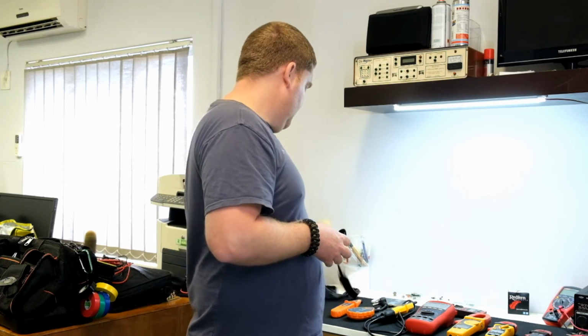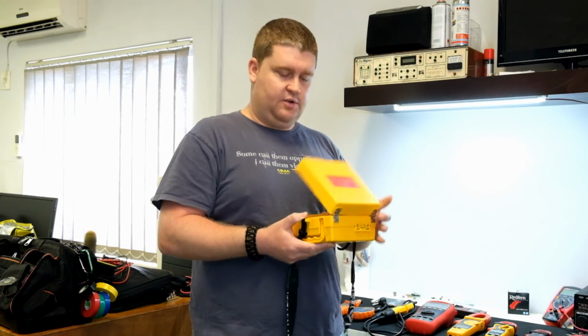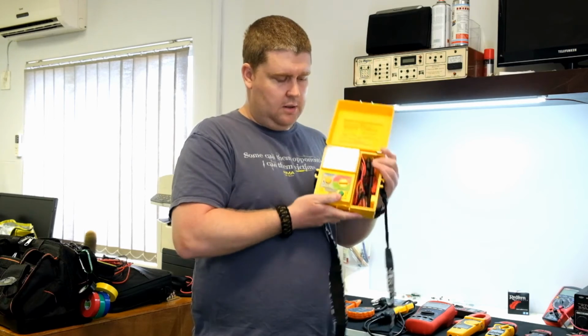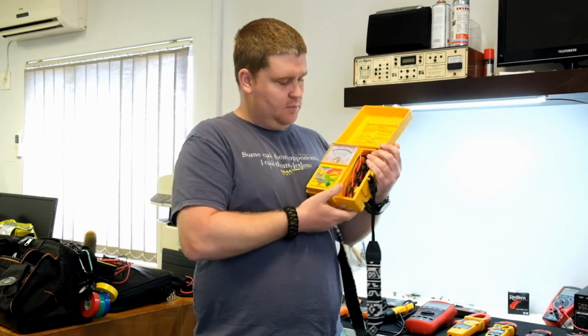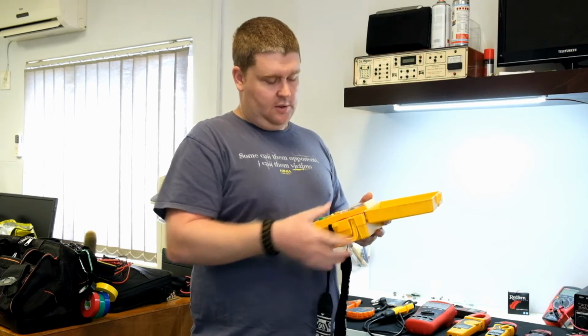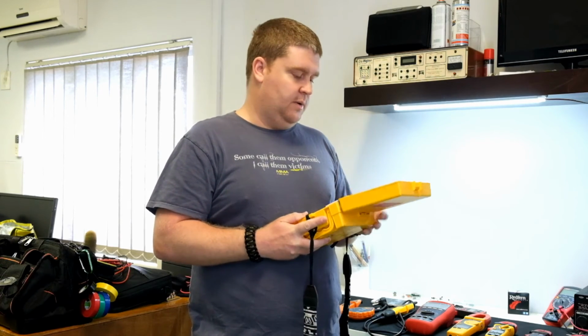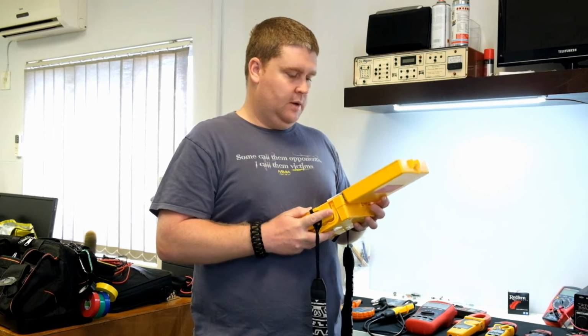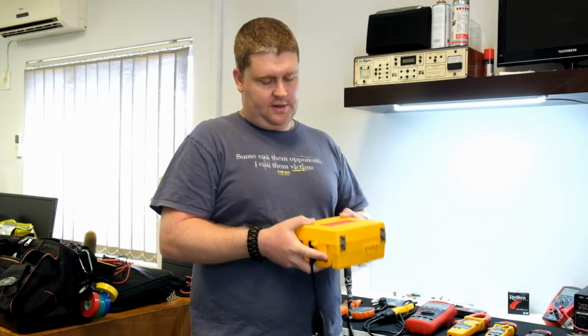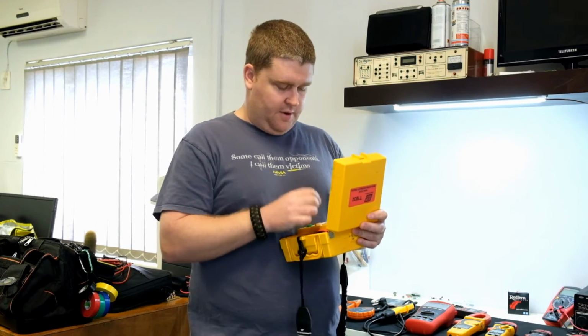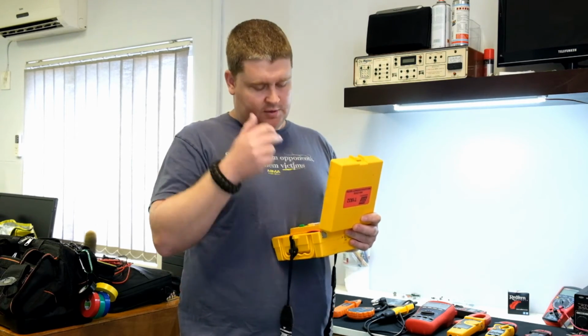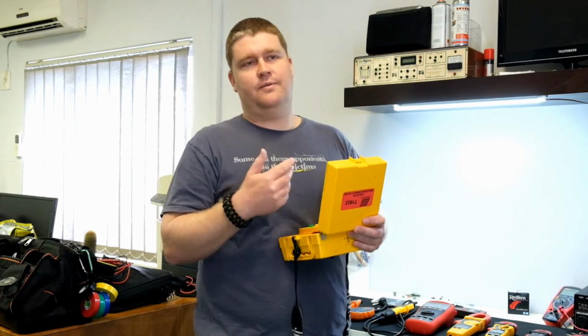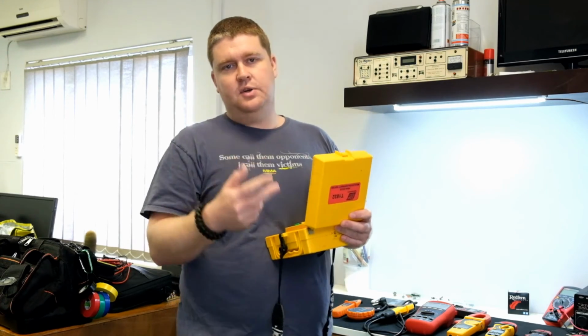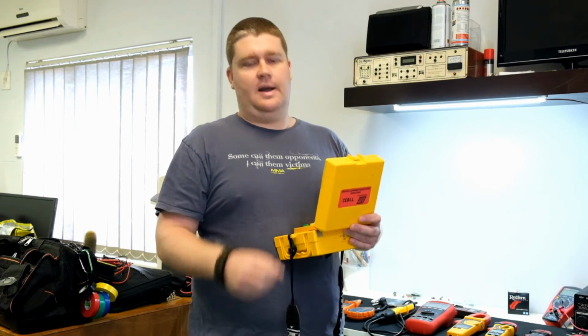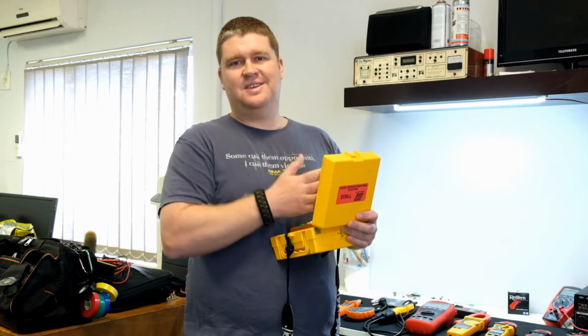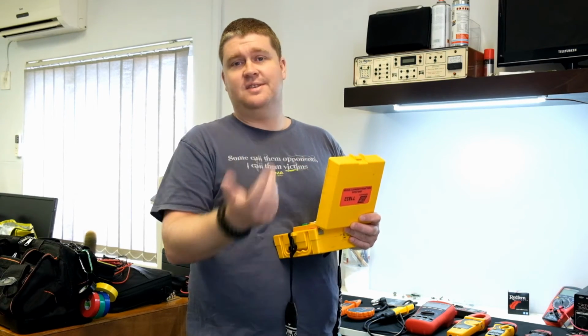Then over here we have the Toptronic insulation resistance tester. Analog. I like the analog meter. This one here you would basically connect to the circuit, obviously making sure that you don't have any sort of electronics connected to that circuit. And then you could select your range 250 volts, 500 volts or 1000 volts, and you could basically inject that 1000 volts, 250 or 500 volts DC into your wires and check if there's any breakages in the wires. Because you would get an actual resistance of your insulation, an insulation test resistance at that potential.